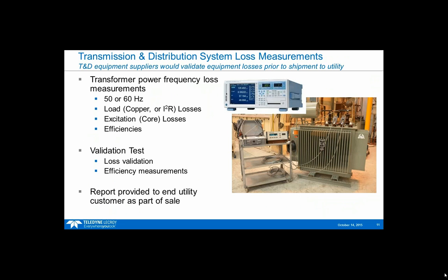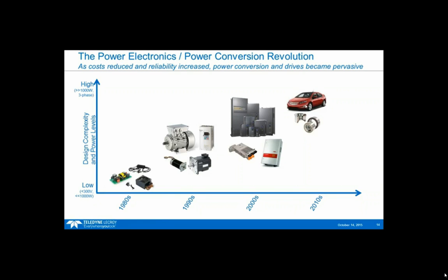Typically in this system, to measure 50 or 60 hertz systems, there'd be something used to measure the core and the copper losses of that, and that would be a power analyzer, and that device was historically made to measure 50 or 60 hertz power line frequencies and do validation tests and present a certificate to, let's say, a utility or end customer as part of the, say, 1980s, moving up in complexity and power levels and voltages and number of phases as the decades progressed.